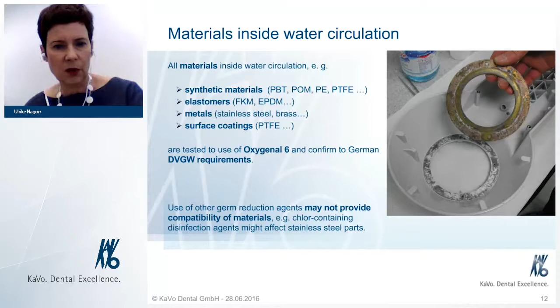good cooperation with the different materials that are used in the treatment units. And we have many of them. Of course, we have some synthetic materials as the tubings, the instruments tubings. We have elastomers, some sealings inside the tubings, the metal parts, of course, stainless steel or brass, and surface coatings as, for example, the Teflon layer that KaVo instruments tubings do have inside in order to avoid or minimize the attachment of biofilm already construction-wise inside the tubings.